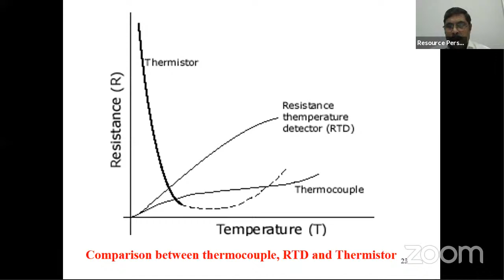Okay, now we will move on to the thermocouple. Basically, thermocouples are the most commonly used passive sensors. It's not like an instrument, it's a simple wire, just similar to an electrical wire. This thermocouple works based on the Seebeck effect. So we have to take two dissimilar metals, and then you form a junction. And when these two junctions are maintained at different temperatures, there will be an EMF induced in the circuit. This induced EMF is directly proportional to the temperature difference between the two junctions.